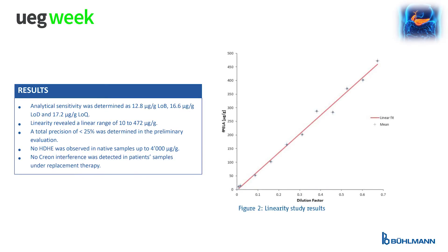Several analytical studies were performed during the optimization phase to evaluate the performance of the assay. Analytical sensitivity was determined and a limit of quantification of 17.2 micrograms per gram was established. A total precision of less than 25% was determined in the preliminary evaluation.